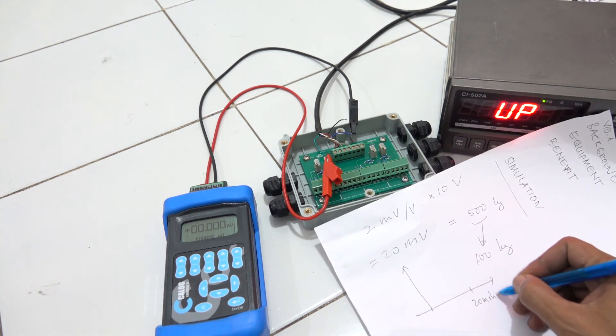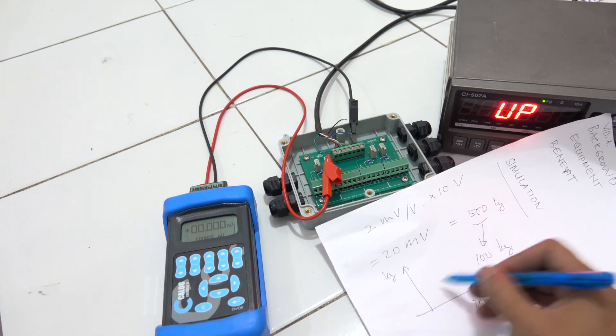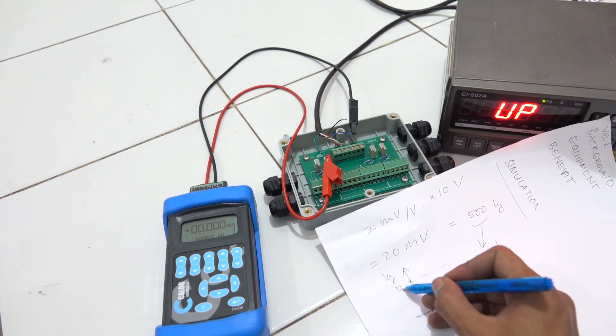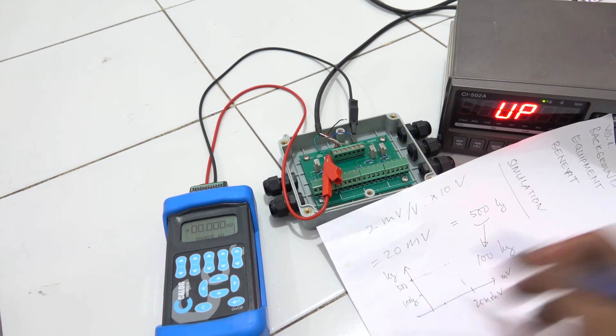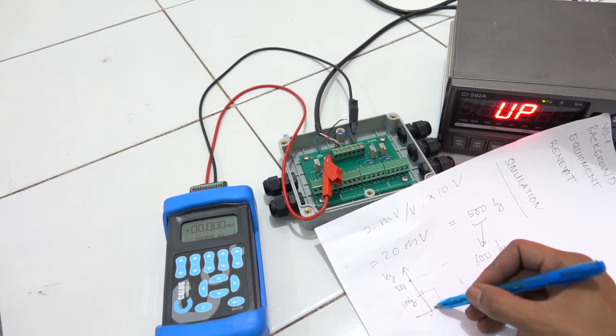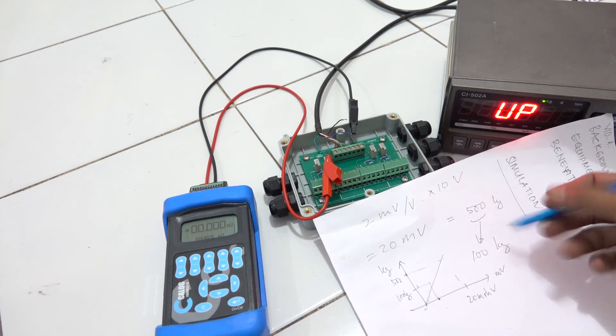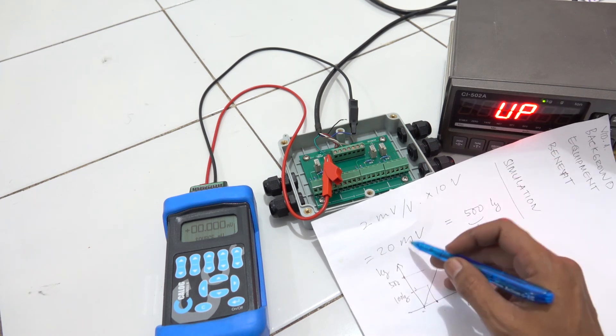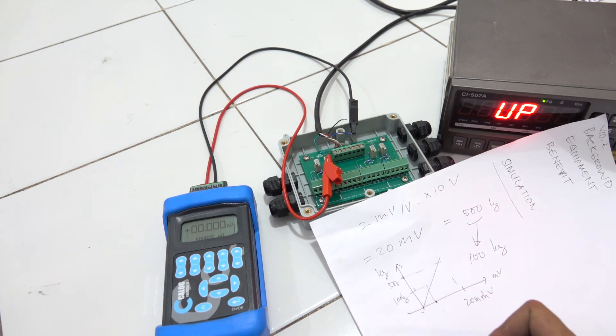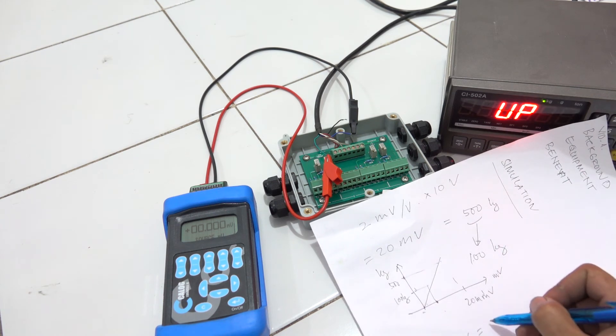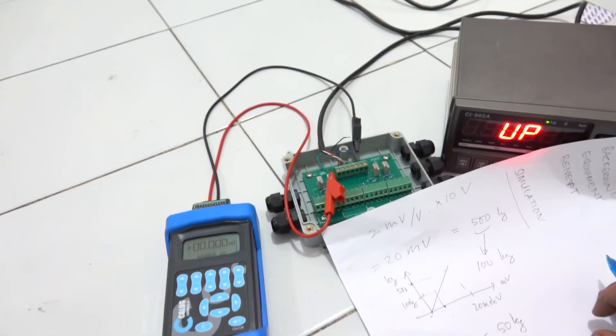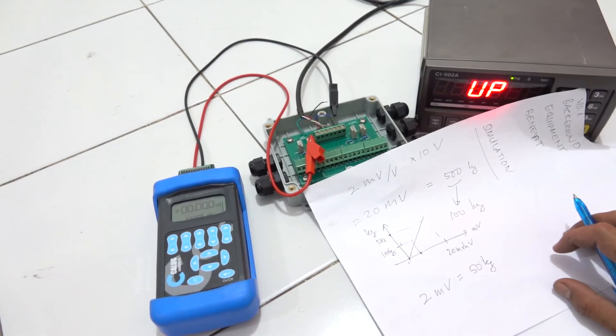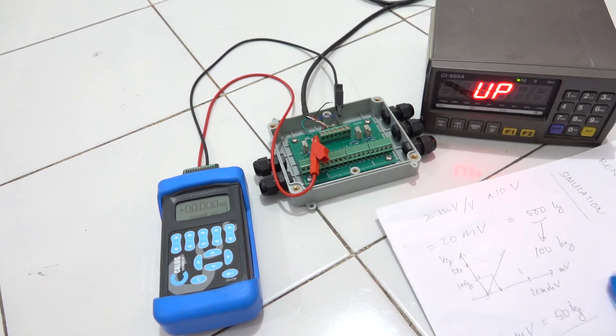20 millivolt here is millivolt, and your kg is 500. How about if 100 kg, how many millivolt will it be? So let's say this is ideally linear. You can easily calculate that here. 20 millivolt, 500 kg - if you divide it, it means 2 millivolt per 50 kg. So 100 kg is 4 millivolt.